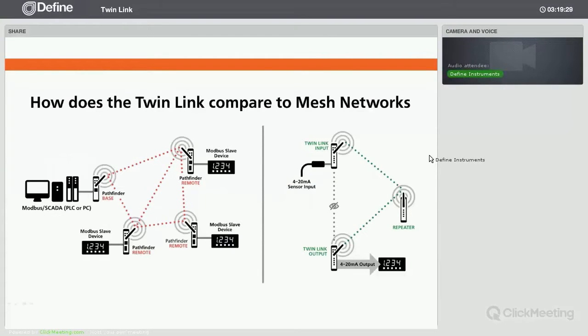In this diagram, you can see the simplicity of the TwinLink and its advantages over the more complicated mesh network systems. As you can see on the left-hand side, mesh networks are typically used to get data from devices that support Modbus. And to read Modbus data from each device requires a Modbus master, such as a PLC or SCADA system. These Modbus masters have to be programmed by a PLC programmer or a software engineer. The simplicity of our TwinLink is that the inputs are analog, such as 4 to 20 milliamp, RTD, or thermocouple. These inputs are converted to a digital number, and the TwinLink transmits them wirelessly to the receiver unit. This unit then reconverts the signal to a standard 4 to 20 milliamp output. No PLC programming is required, making the use of this unit accessible to a wider range of engineers and technicians.